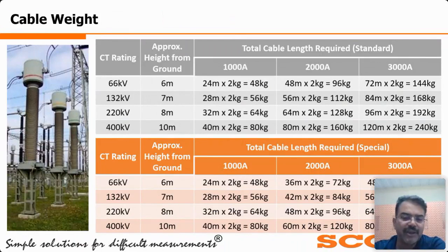When using standard cables, people consider a current density just below 4, for safety, because the cable heating used to take place, and normal PVC can withstand only up to a certain temperature, maybe 60 or 70 degrees. But class F insulation can withstand up to 200 degrees. So from that angle, we can go to a higher current density and achieve more.